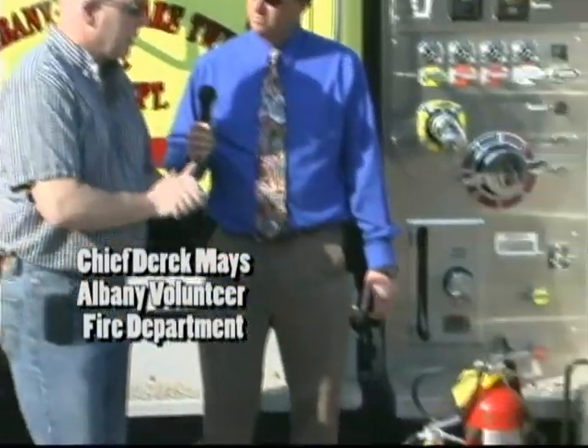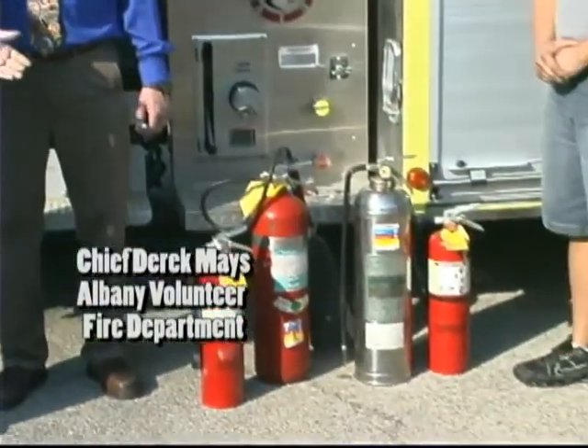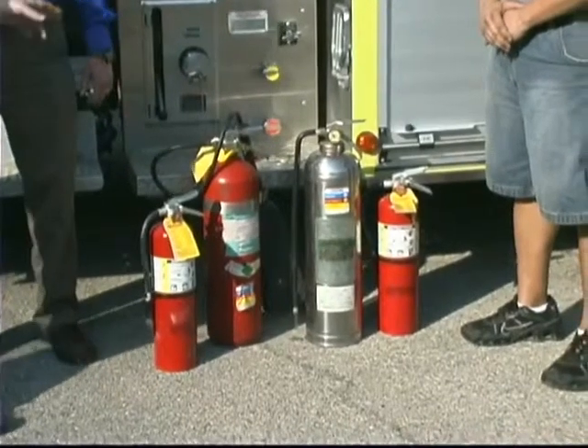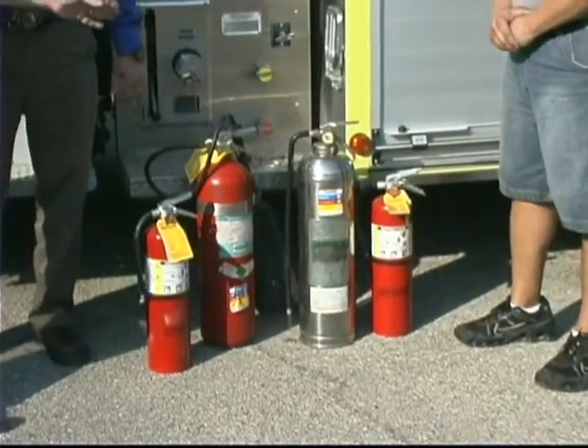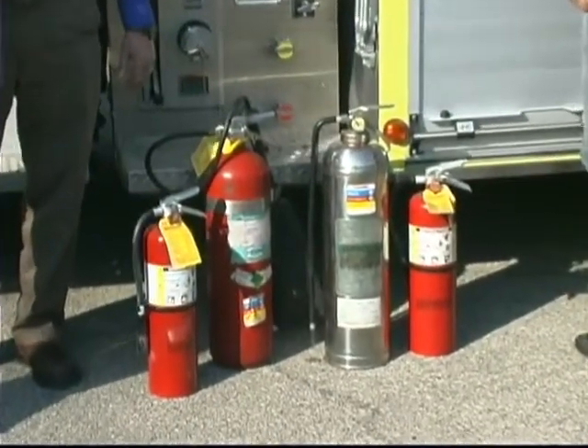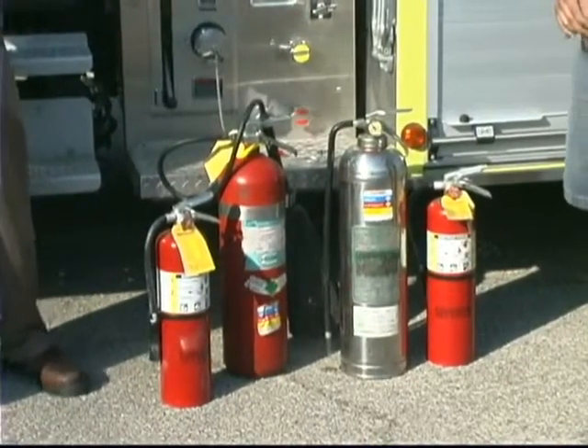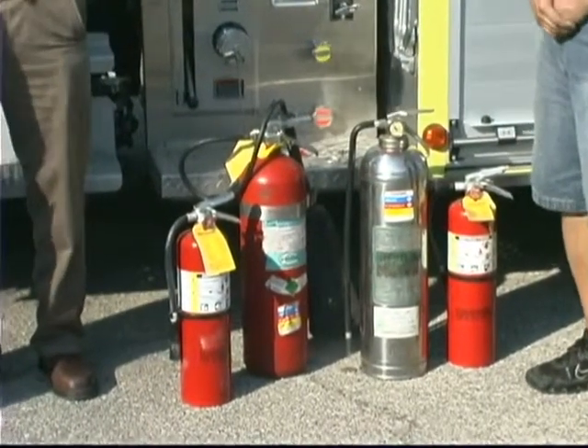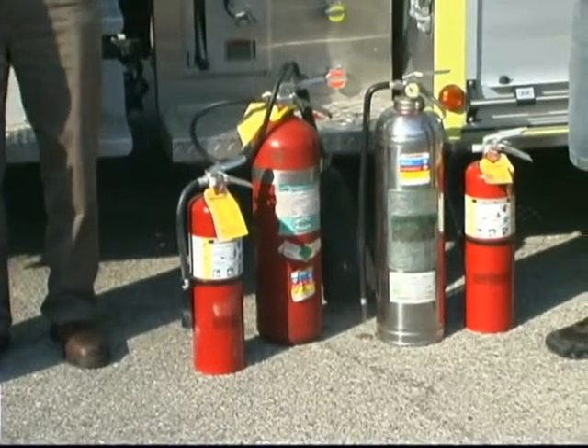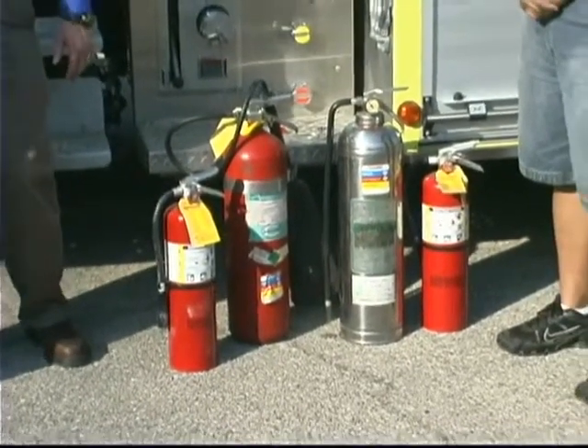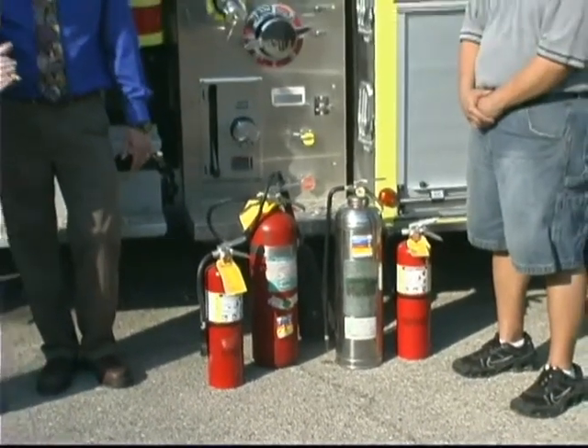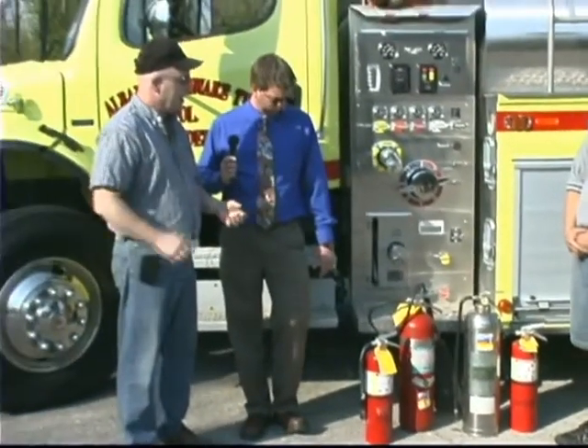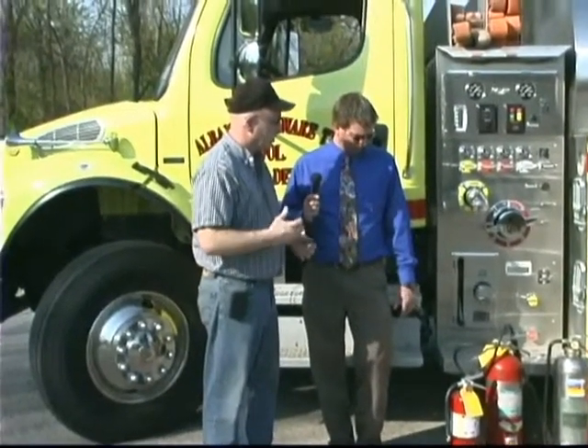Sure, Jason. The first type we have here is an ABC. It's a common 10-pound extinguisher that you'd find. It's a dry chemical extinguisher. You've got a CO2 extinguisher next to it and a water extinguisher next to that. So when you say ABC, I know we hear that term occasionally and we'll see those on the packaging in stores. What does the ABC mean? ABC is a rating of what the fire extinguisher is designed to put out. A being common combustibles, B being your liquids or your greases, and C being a charged electrical.